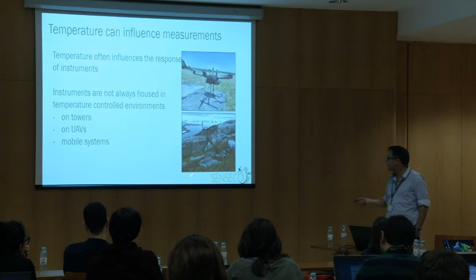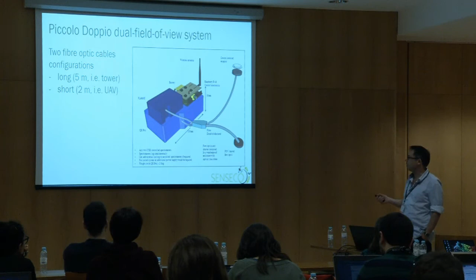The light source is this custom-built lab sphere integration sphere with this 10-watt IHLS. I don't even know what IHLS means, to be perfectly honest. Light source is what is used in terms of, we talked a little bit about how often you should be doing the calibration and so on. So the approach that we've been trying to adopt is to do a proper lab calibration once a year, but use this Calvel sphere that is portable and can be sent out and posted out, so after campaigns and so on and so forth. Check your system with this one, and then that is linked back to the calibration back in the lab. So to try and maintain this traceability through the course of the year or under different conditions and so on and so forth. And as we're increasingly becoming aware, and Laura mentioned it, as you move your system around, take things apart, put it together, things change and so on and so forth. So I was testing that using this light source.